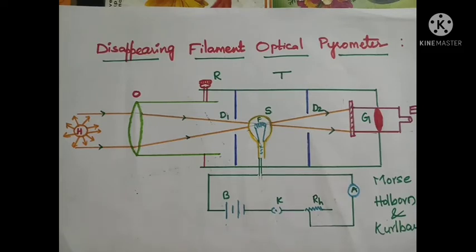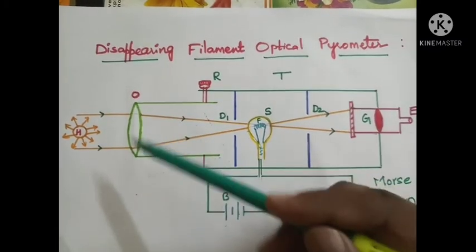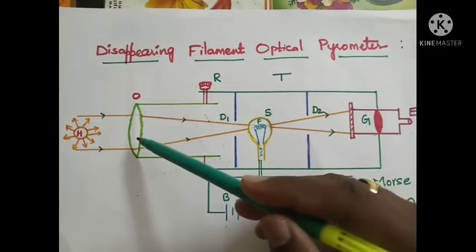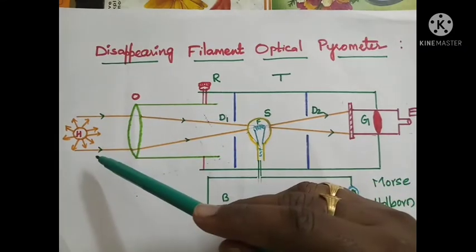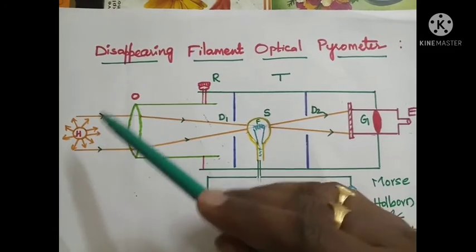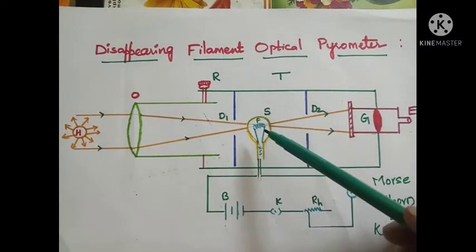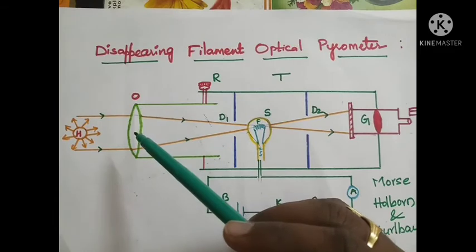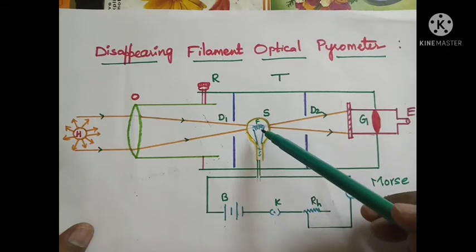Now let us see the working of this instrument — how we can measure temperature with it. The objective lens of the pyrometer is directed towards the hot body H. With the help of the screw, the position of the objective is adjusted so that the image of the hot body is focused on the filament.